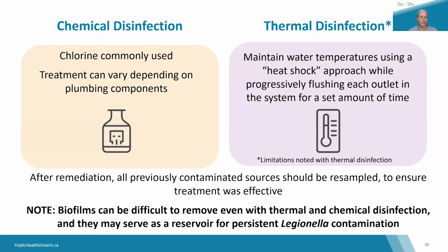The level of chlorine and the amount of time that it's applied varies. And depending on the system, it could be dosed at a low concentration for a number of hours or a high concentration for a shorter duration of time. And again, it's very system dependent, and these decisions can be supported by best practice guidance and the expertise of water system consultants. After disinfection is complete, all outlets are flushed and returned to normal operation. Thermal disinfection can also be used. It involves significant increases in temperature throughout the entire system for a set period of time, and then flushing the system until normal temperatures have returned.